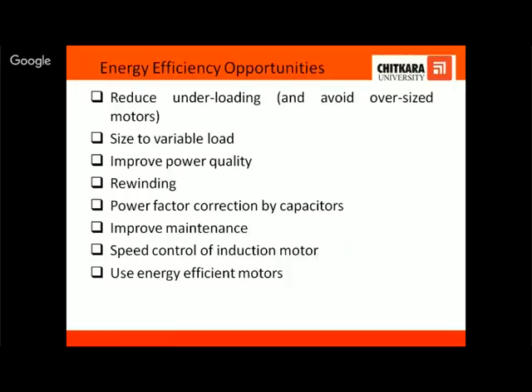Now I have listed some of the energy efficiency opportunities and I have discussed each opportunity one by one. The first thing is to reduce underloading, or you can say avoid oversized motors, because if the motor is underloaded then the efficiency and power factor go down. Then size the motor to the variable load, because sometimes the load is not constant. That part I discussed in that point only. Then power quality should be better, because if the power quality is not good, with voltage or current unbalances, that will affect the performance of the motor. Then the quality of rewinding affects the motor performance. Then power factor correction by capacitors. Then maintenance needs to be improved for the motor. Then there is speed control of the induction motor. Then at the end we say use energy efficient motors.